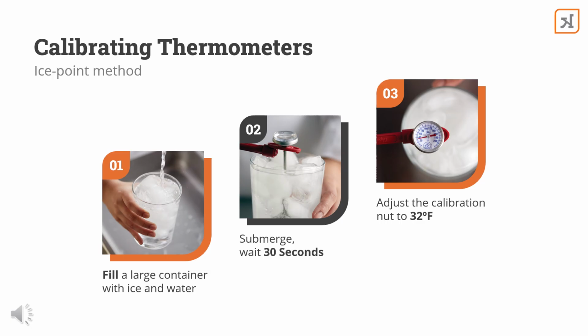Add ice and tap water to a container. Make sure the sensing area is submerged. Be careful to not let the stem or probe touch the container. Wait 30 seconds or until the indicator stops moving. To calibrate a bimetallic stem thermometer, adjust the calibration nut to 32 degrees. To calibrate a thermocouple or thermistor, follow the manufacturer's directions.